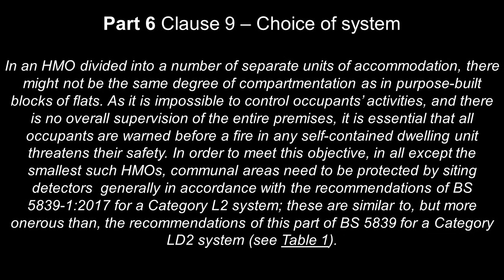Well, let's go to Part 6, clause 9, choice of system. It tells you what system you should install in different properties. In an HMO divided into a number of separate units of accommodation, there might not be the same degree of compartmentation as in a purpose-built block of flats, as it is impossible to control occupants' activities and there is no overall supervision of the entire premises. It is essential that all occupants are warned before a fire in any self-contained dwelling unit threatens their safety. In order to meet this objective, in all except the smallest HMOs, so if it's a really small HMO this doesn't apply, communal areas need to be protected by detectors generally in accordance with the recommendations of BS 5839 Part 1, a Category L2 system. These are similar to but more onerous than the recommendations of an LD2 system in Part 1, in Table 1.